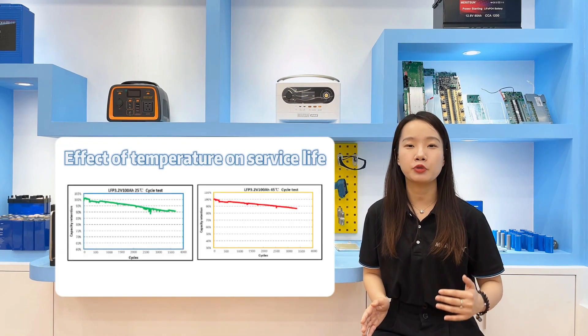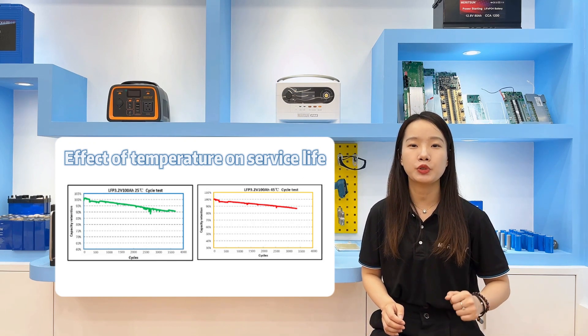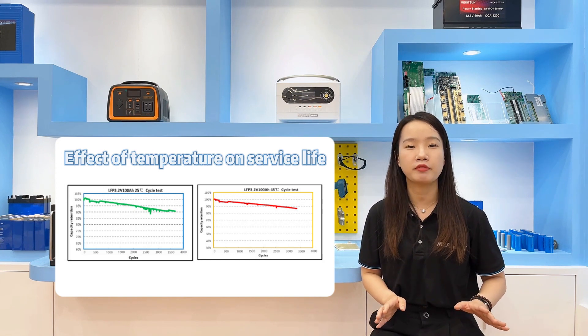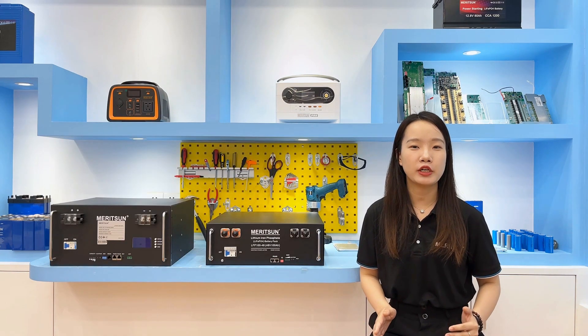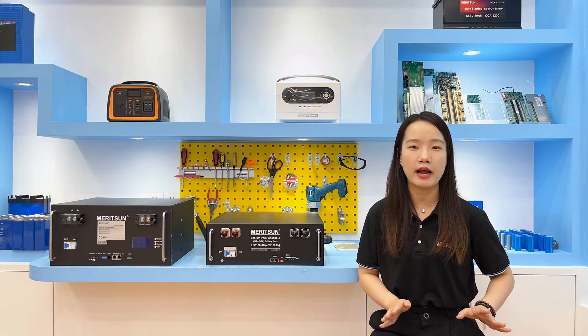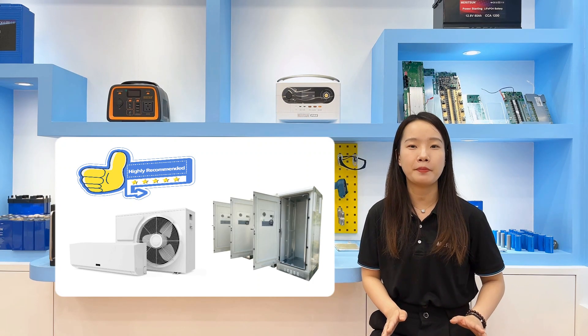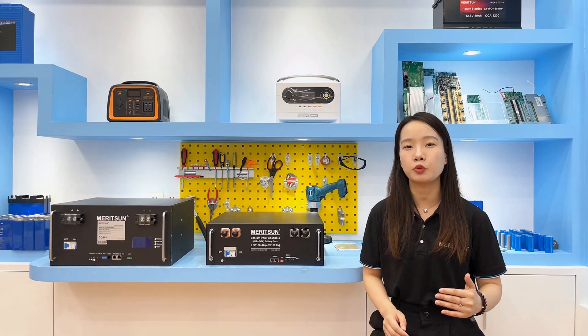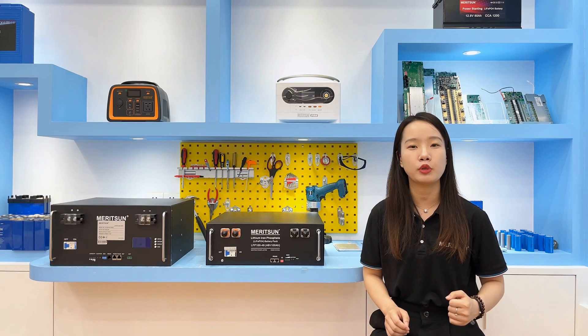The following data illustrate this point. A certain type of lithium iron phosphate battery is charged and discharged at 25°C and 45°C, and the retention rate of capacity will be different after 1,000 cycles. Since ambient temperature is one of the key factors, the battery system should be installed indoors as much as possible. We can also equip it with an air conditioner or constant temperature cabinet to keep the batteries at a certain temperature — normally we recommend 20 to 25°C.